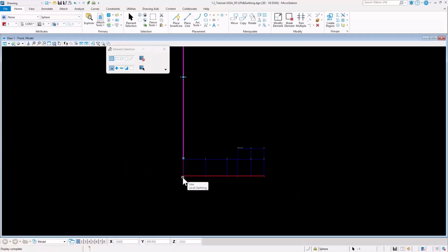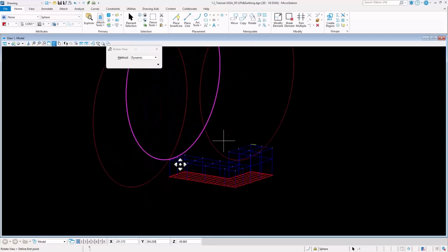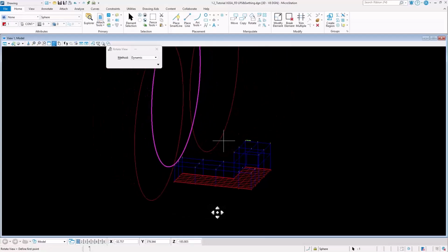This is one methodology that is relatively common in the industry, but there's a little bit of a concern, is that we're looking at a sphere that's a three-dimensional object. We're trying to protect a structure that is a three-dimensional object. And if we're evaluating it as two-dimensional views, we can have holes in our analysis. So what I mean by that, we can really illustrate if we go through a case example.